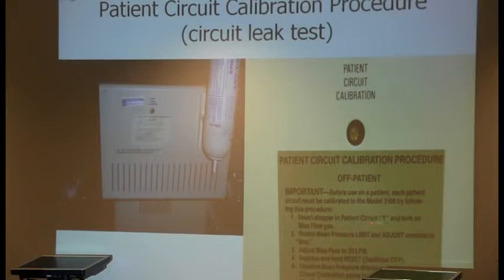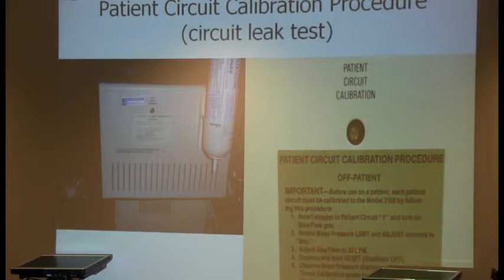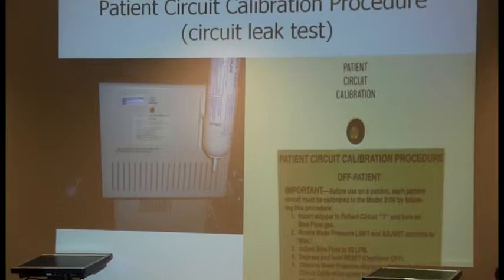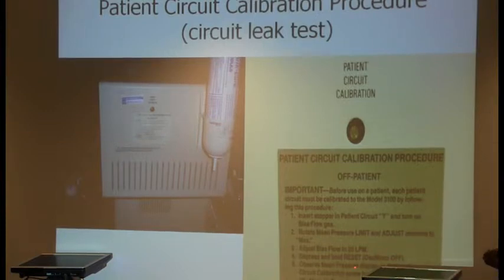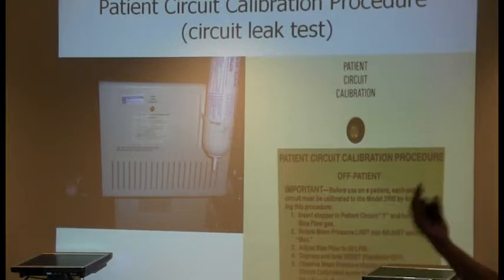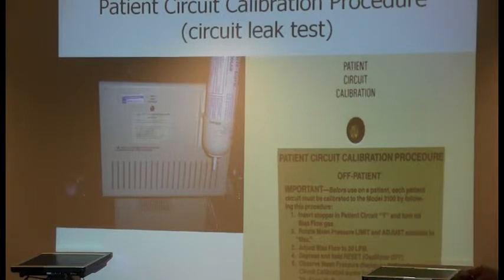Insert stopper at patient Y and turn on the bias flow gas. Rotate mean pressure limit adjust controls to max. Set your bias flow at 20 liters per minute. Depress and hold the reset button while the oscillator is off. So do not start the piston. If you start the piston, then I already know that you don't know what you're doing. Observe your mean pressure displayed so that it reads 39 to 43. So if your circuit is intact, there are no major leaks, you'll get this setting, 39 to 43. That means that you're good to go.